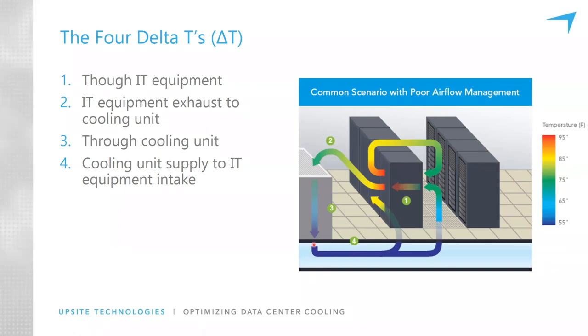Delta T4, why does the air heat up so much from the time that it leaves the cooling units before it gets to the intakes of IT equipment? It is because of exhaust air recirculation. Hot exhaust air is finding its way into the cold aisle flow path approaching the IT equipment, and it's mixing with and warming up that conditioned air.